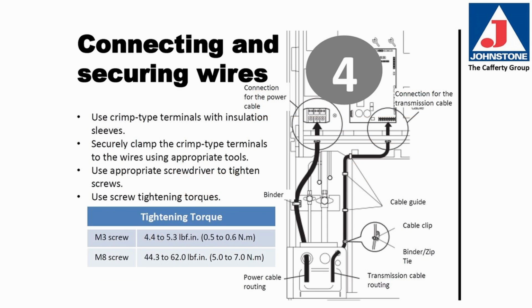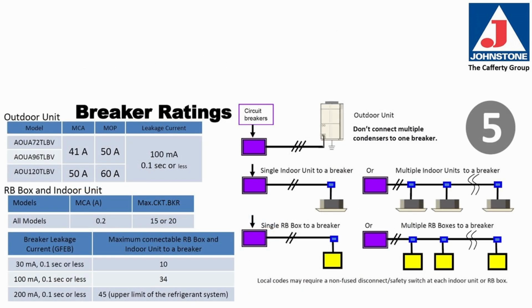Connecting and securing wires. Use crimp-type terminals with insulation sleeves. Securely clamp the crimp-type terminal to the wire using the appropriate tool. Use the appropriate screwdriver to tighten the screws, and tighten to the correct torque specs, which can be found in the installation manual. Circuit breaker ratings.